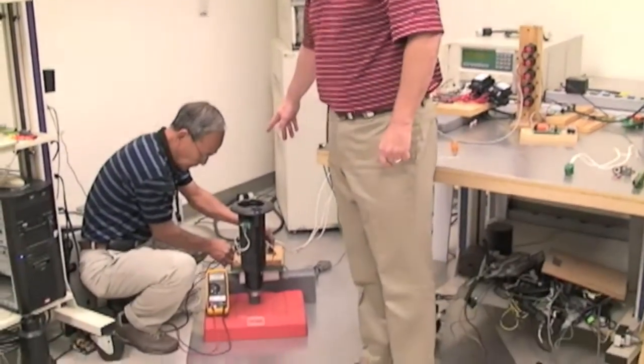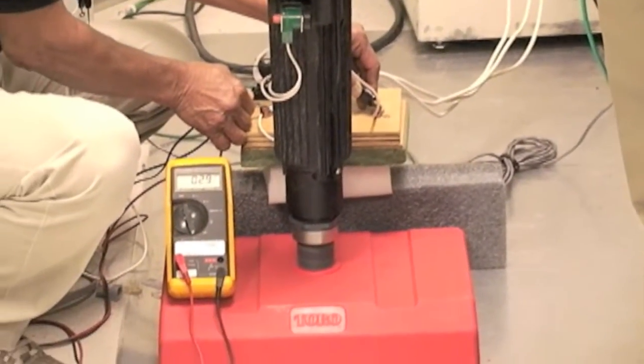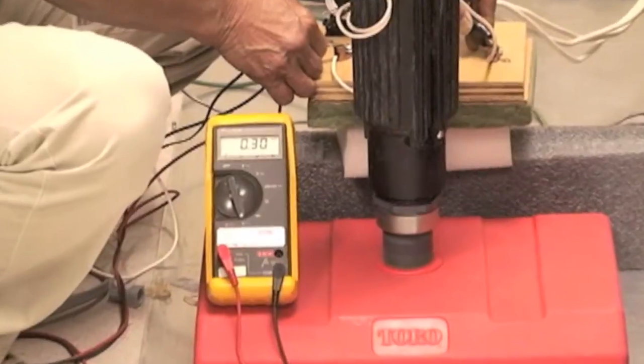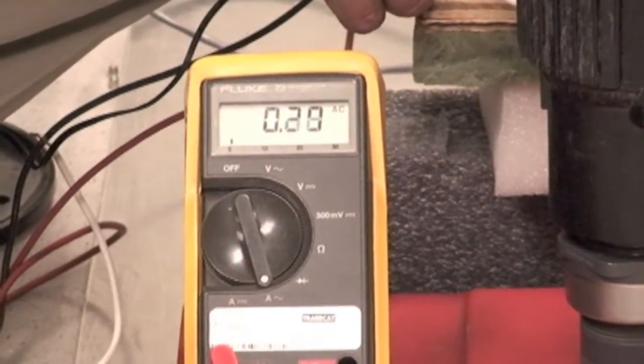We start by applying a 24 volt AC source to the solenoid to measure the amount of current that it's drawing to confirm that it's operating properly.